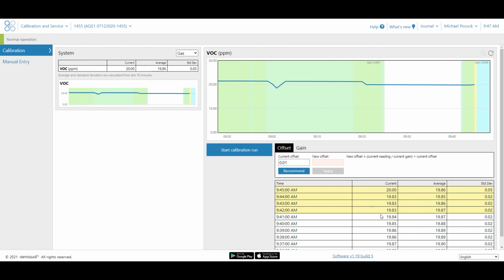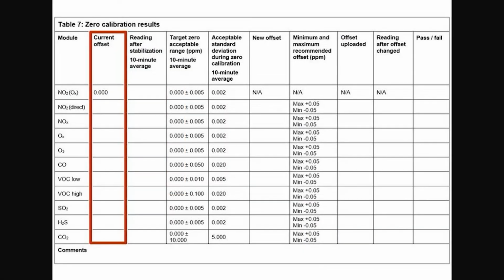I just want to show you a couple of tables at the end. This is just for reference. These are available on Aeroqual support if you look at calibration, or in the online manual. This is where you can see what the manufacturer recommends. I was using these numbers. For a 0 calibration, you want to be within plus or minus 0.1 ppm, and you want your standard deviation to be 0.02. So very stable readings.